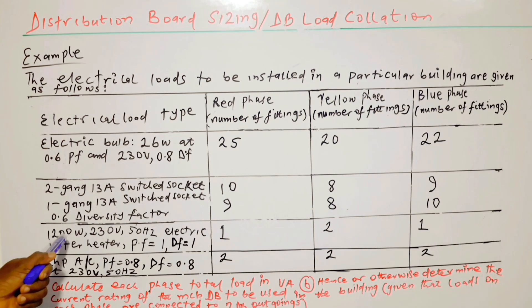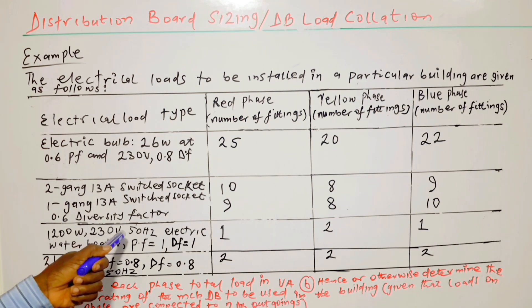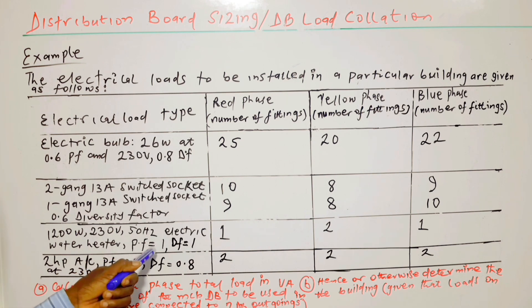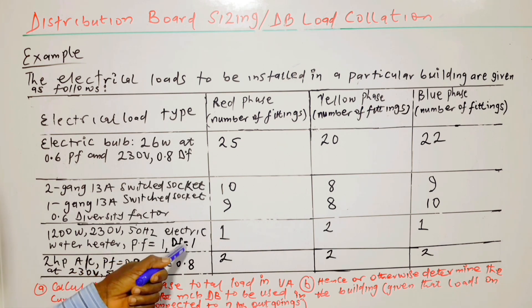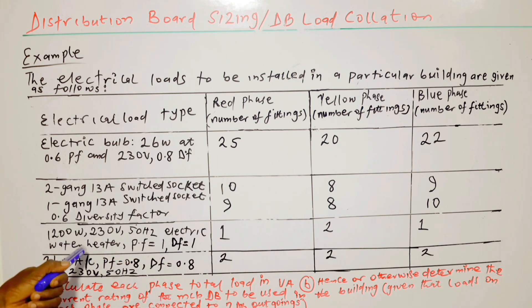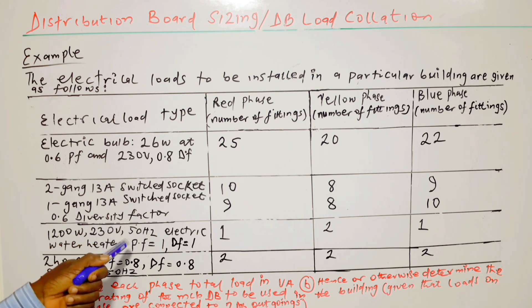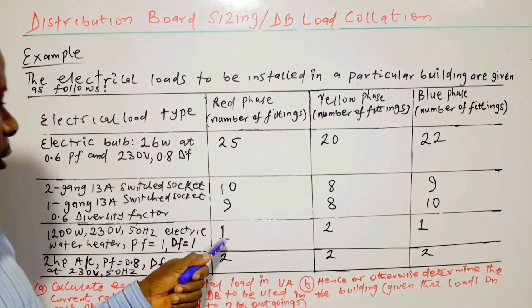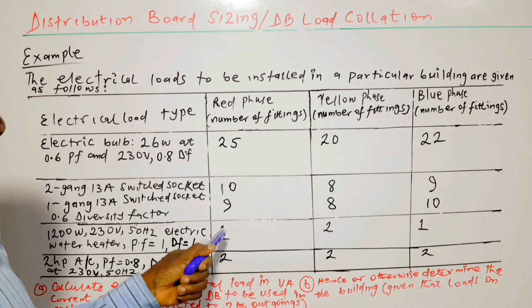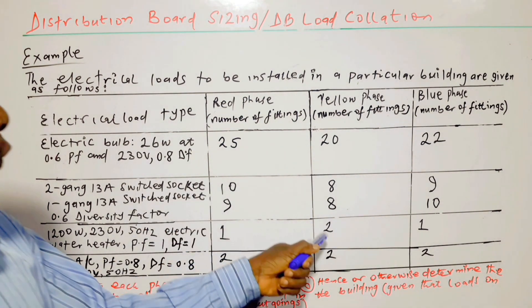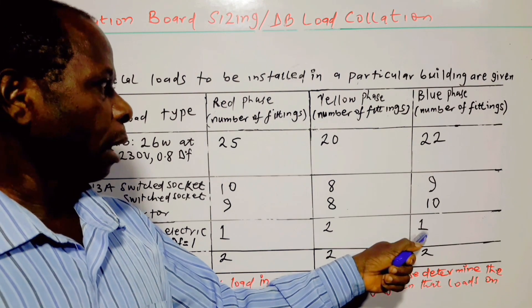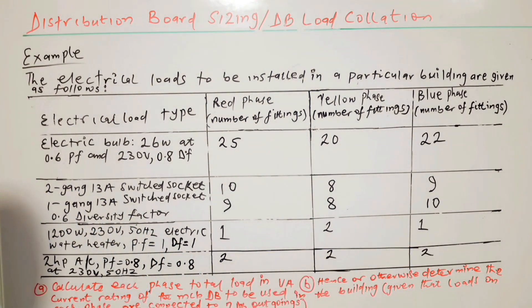1,200 watts, 230 volts, 50 hertz electric water heater. Power factor is equal to 1, diversity factor is equal to 1. It's a heating load — that's why the power factor is 1. Any heating load has a unity power factor. So we have 1 water heater on red phase, 2 on yellow phase, and 1 on blue phase.